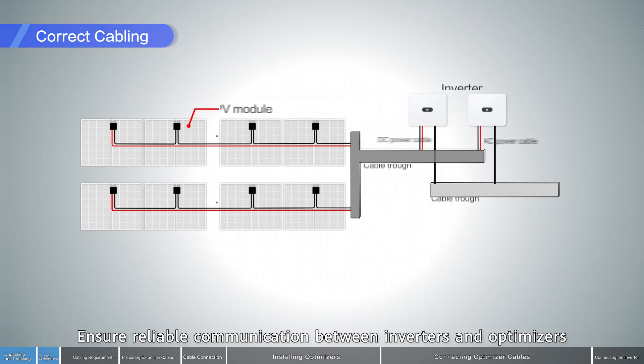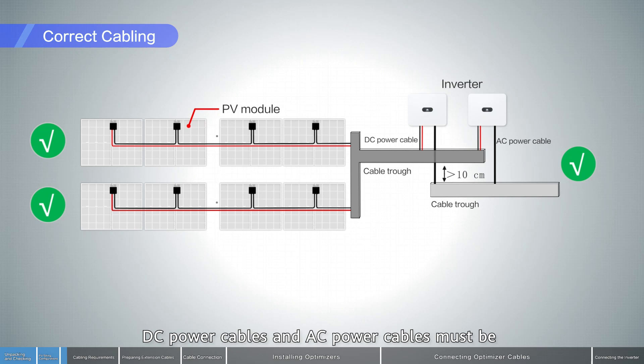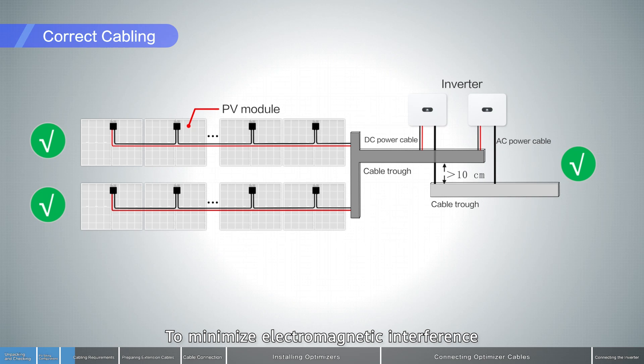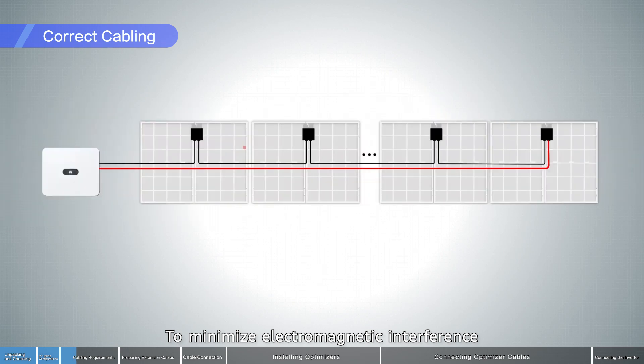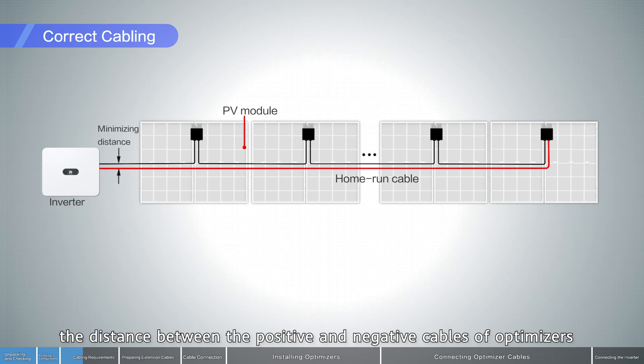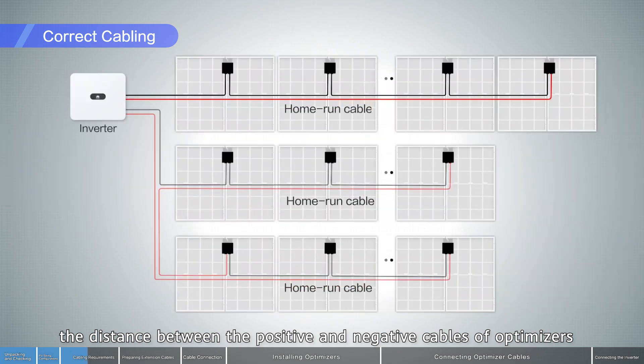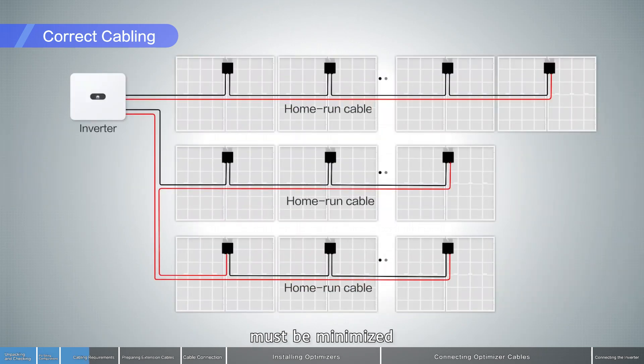Ensure reliable communication between inverters and optimizers. DC power cables and AC power cables must be routed in different troughs with a spacing of more than 10 cm to minimize electromagnetic interference. The distance between the positive and negative cables of optimizers must be minimized.